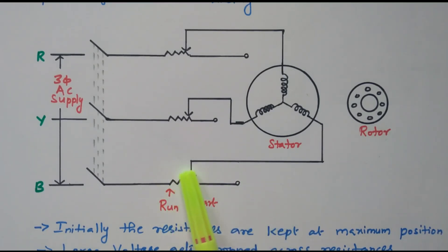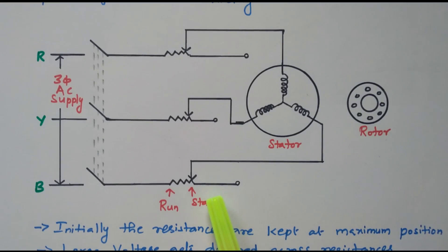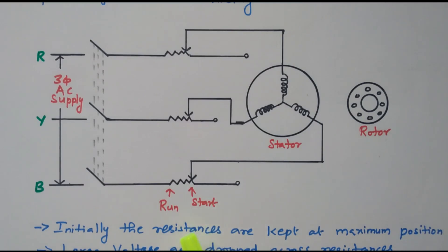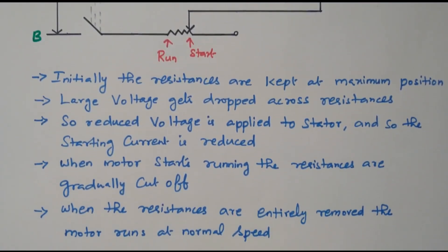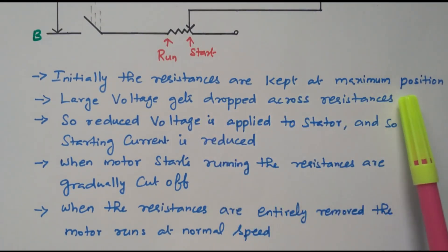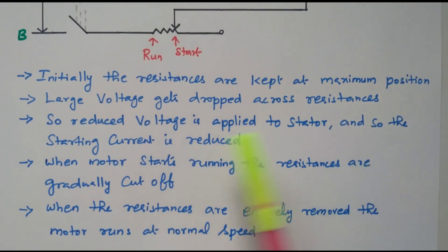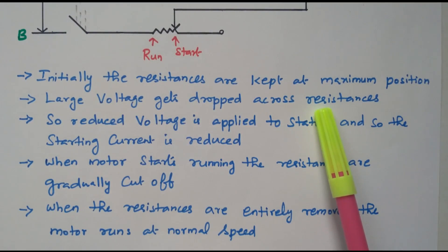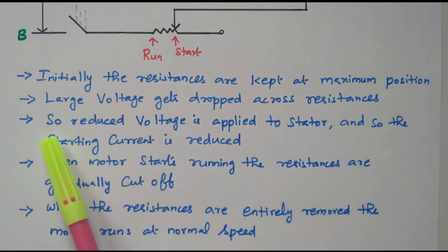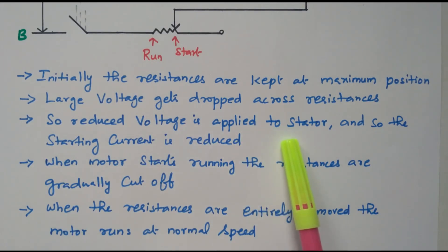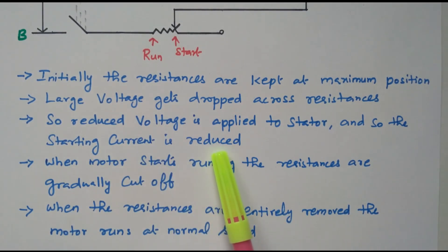Finally, the full rated voltage is applied and full rated current is taken by the stator. Initially the resistors are added so that the voltage applied to the stator is limited in order to limit the high starting current. Thereafter the resistors are slowly decreased, the voltage gradually increases, so that the current taken by the motor also increases. The main objective is: because of the reduced voltage, the starting current is also reduced.